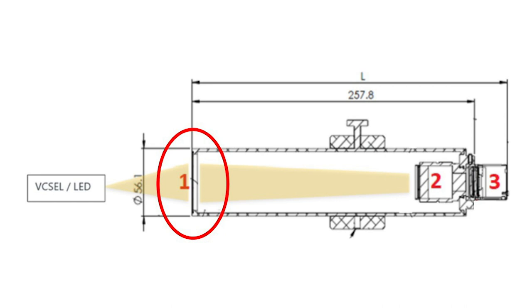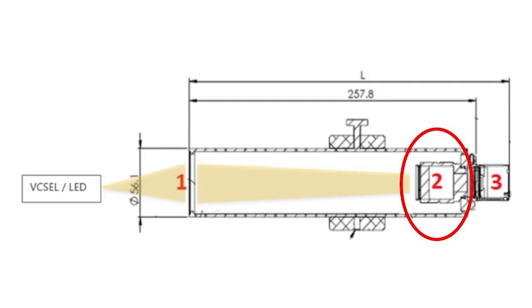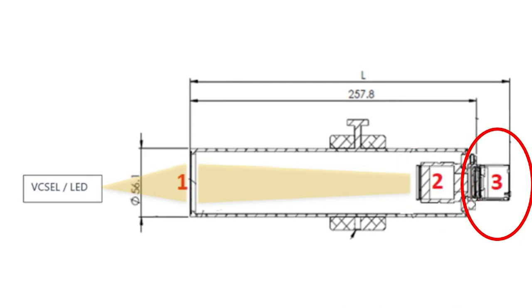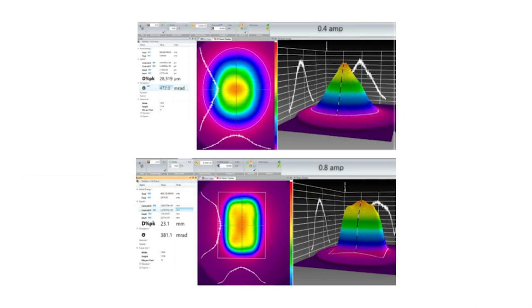Beams are captured on a large 48mm diameter diffusive screen and then re-imaged via CCTV lens through suitable attenuating filters onto the profiler camera. The camera, together with Ophir's BeamGauge software, produces a complete and accurate mapping of the light's intensity distribution.